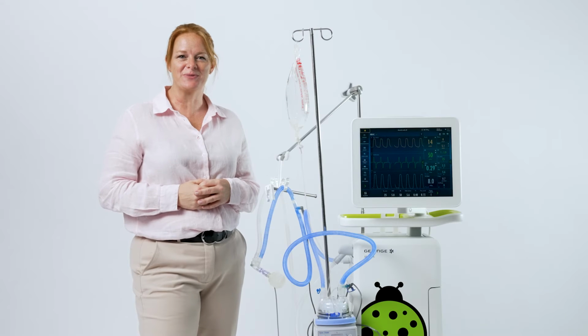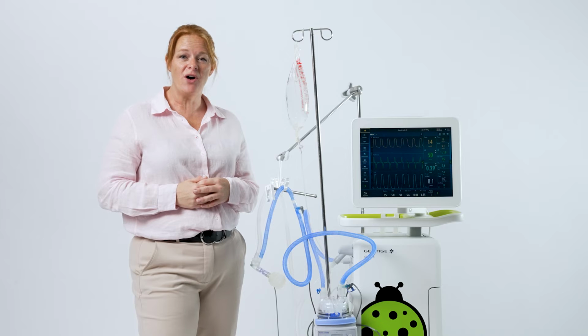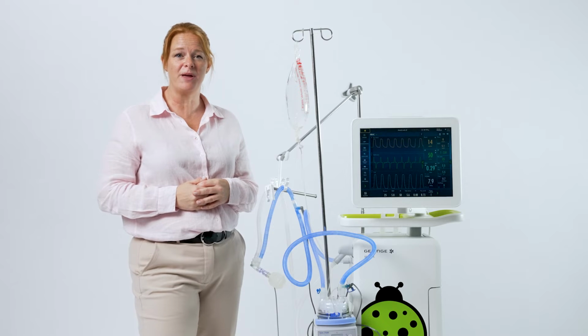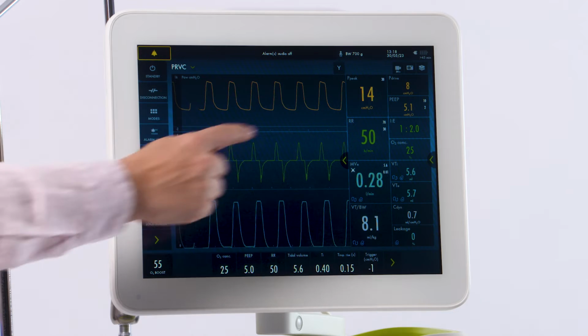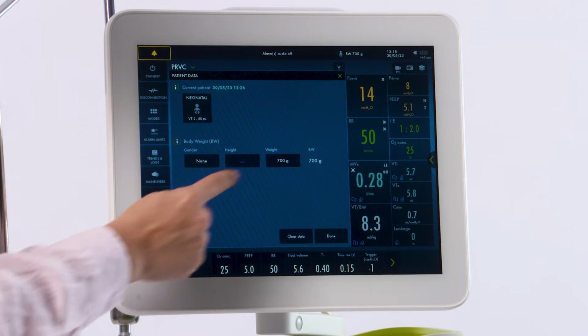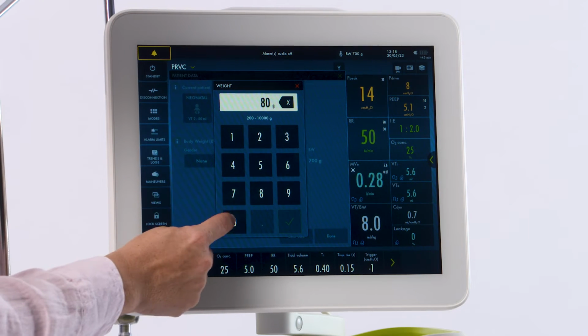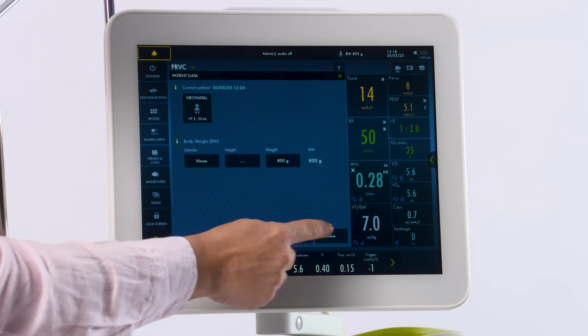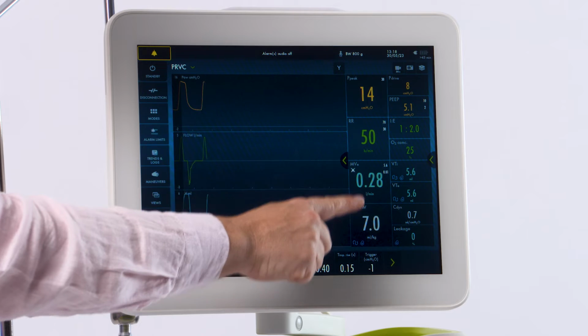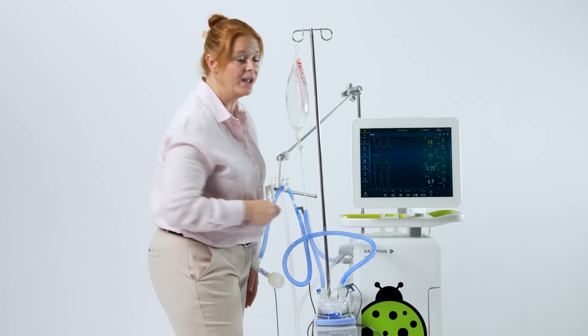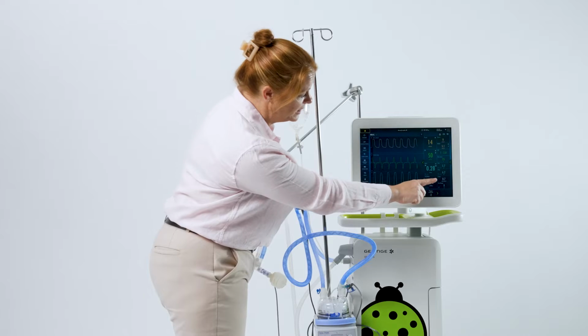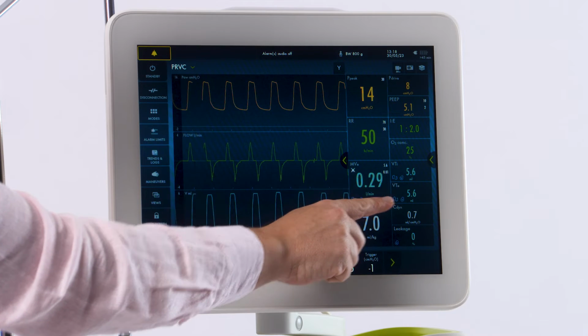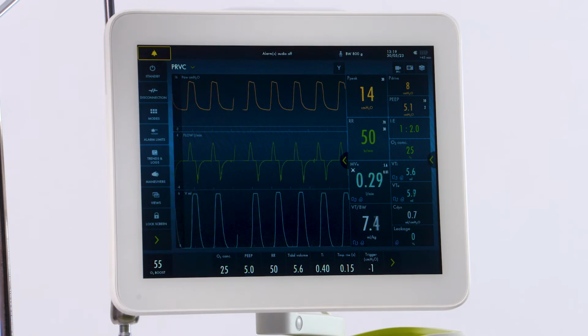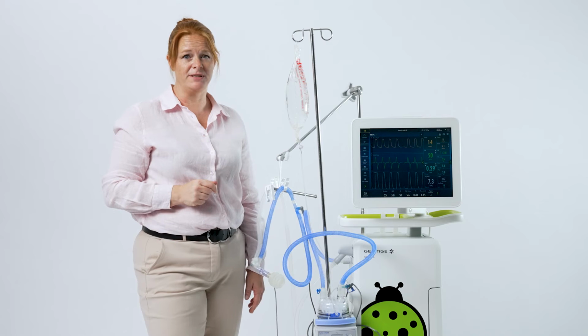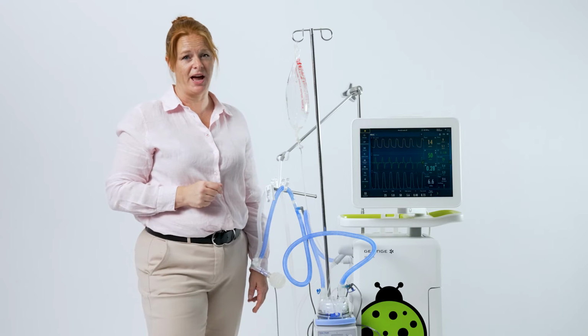We entered the baby's weight at the very beginning, but you can also do it while ventilating as the baby's weight fluctuates. Do this by touching the same spot and adjusting your weight. As you do this, the vent will also calculate breath by breath, mils per kilo, and be trended in your trends as well. You'll also note next to your volumes, you will have an S symbol indicating that the tubing compensation is there and that you're delivering accurate volumes.